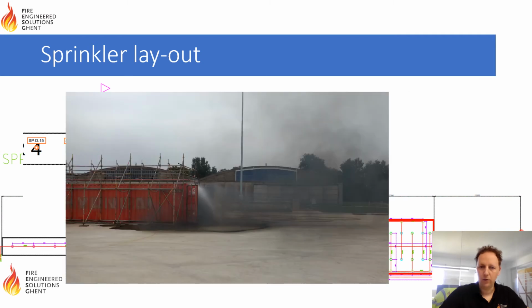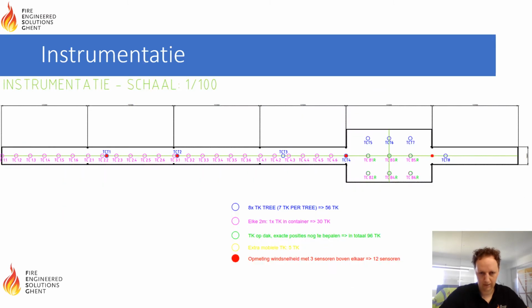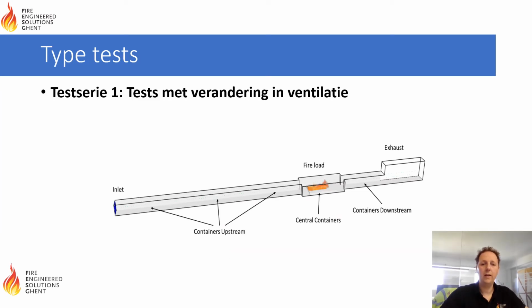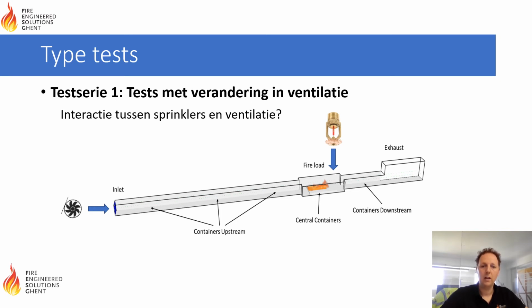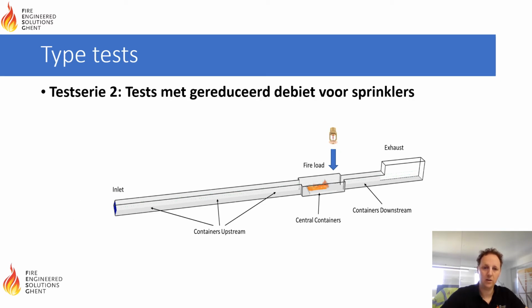We had water flow measurements, etc. We had a lot of thermocouples in place, velocity measurements in place, and thermal imaging cameras. The type of tests we performed, the first series was to look at changing the ventilation and look at how it would affect the sprinkler efficiency, looking at the interaction also between sprinkler and ventilation.